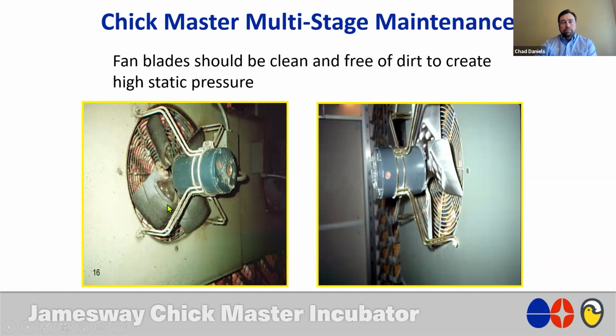Oftentimes, and we've done many different trials and procedures where we've taken an older machine that was in very dirty or poor condition and measured air velocity, measured static pressures, and then went in and simply cleaned it and made it look like our image here on the right. And we've documented anywhere from 10 to 20% increases in static pressure and air exchange rate through the machine. So don't look at this and think, well, my hatch looks okay right now and I'm happy with it. You can't give this enough attention to make sure that everything is clean and in good operating condition.